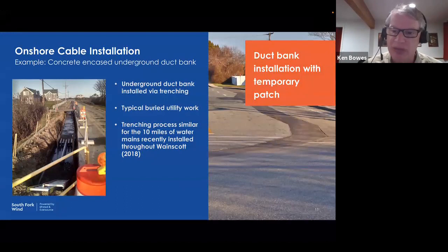Going at a pace of about 100 feet per day, if you do the math over 2 miles, at 5,280 feet per mile, that's a little over 10,500 feet — about 120 days plus or minus to complete this duct bank system in the town roads, and a similar amount on the Long Island Railroad, which has additional complexities due to a much tighter work zone than the town roads.